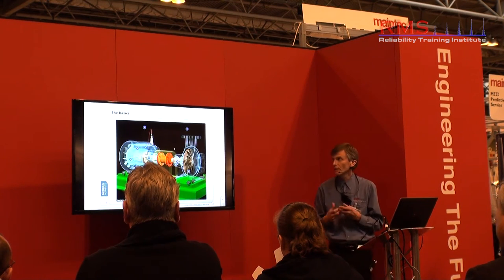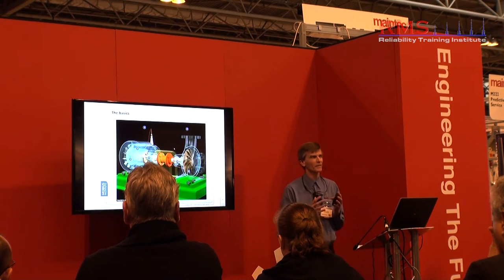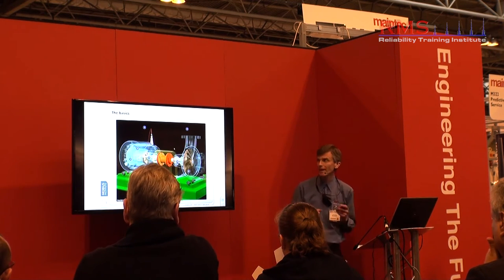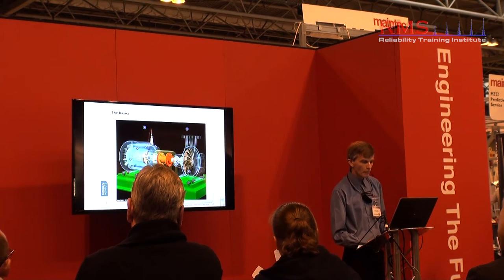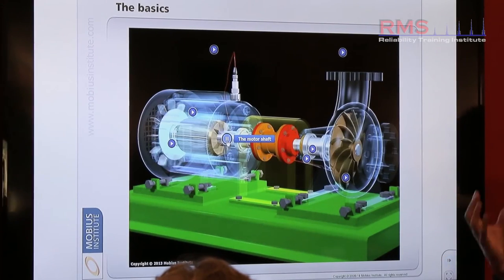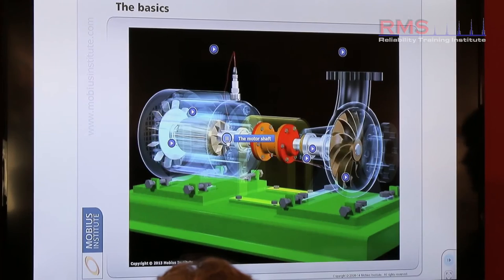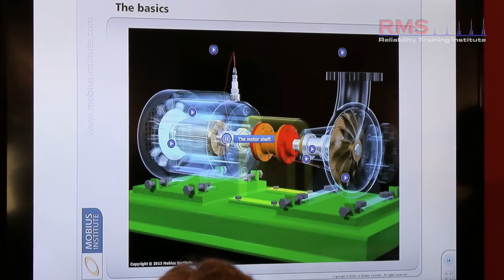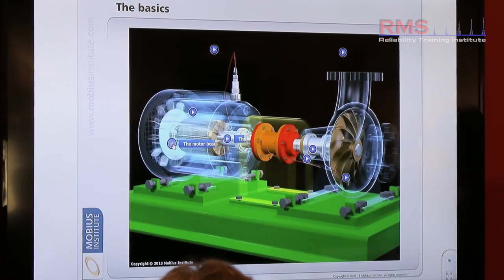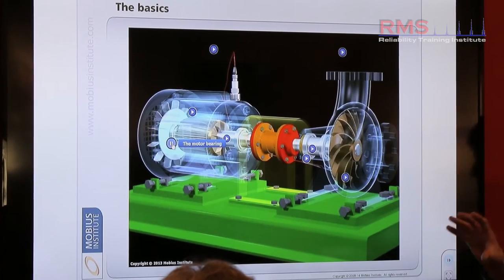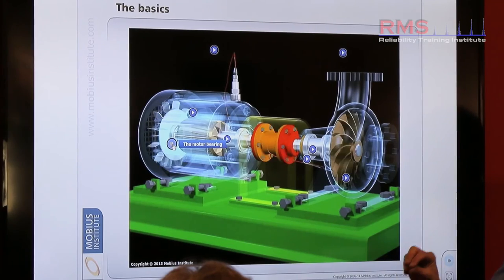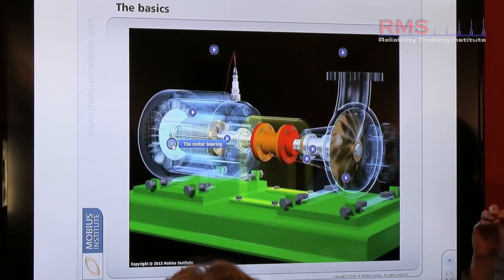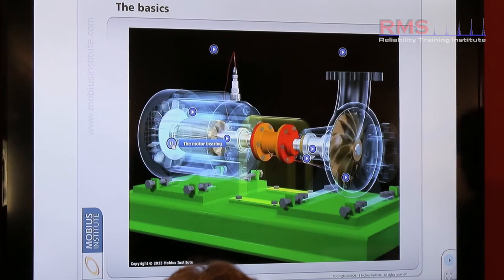So how does it kind of work? Vibration is a strange thing. People think everything's going to shake and move quite dramatically, but maybe that's not the case. If my machine were out of balance, that would cause more of a radial force and I would touch the machine and feel it's vibrating. But if I had a bearing problem, that's not actually going to cause the machine to move and vibrate excessively. It's going to be more localized impacts and shocks due to the bearing that might be damaged. So that's a different heartbeat entirely.